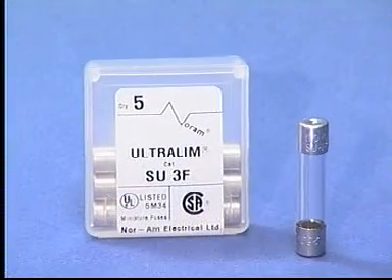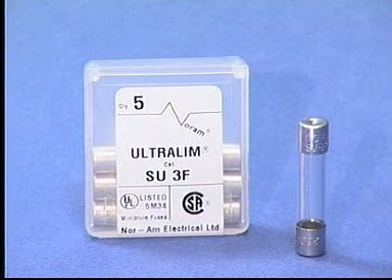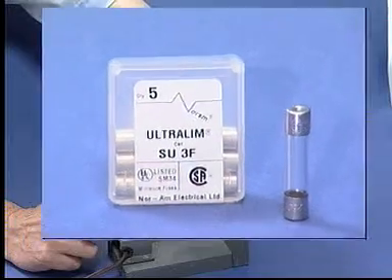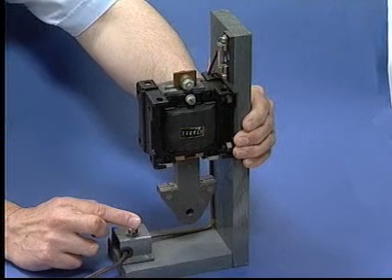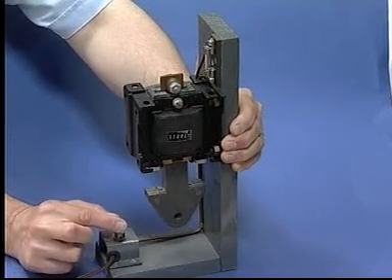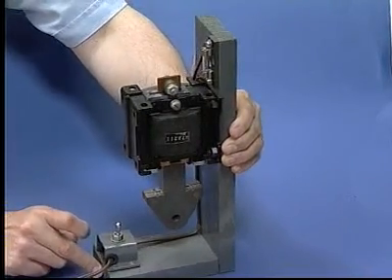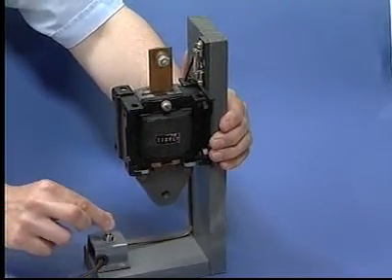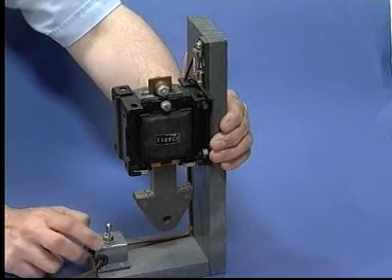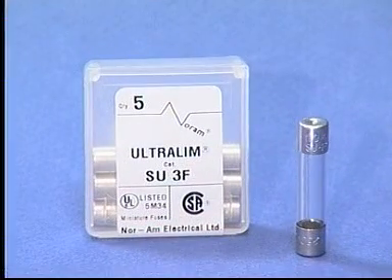For the second test, another fast-acting fuse is used, but sized higher at 300% or 3 amperes. This allowed the solenoid to repeatedly close, since the larger rating increased the fuse's thermal capacity. However, consider the fact that we now have an oversized fuse in the circuit.